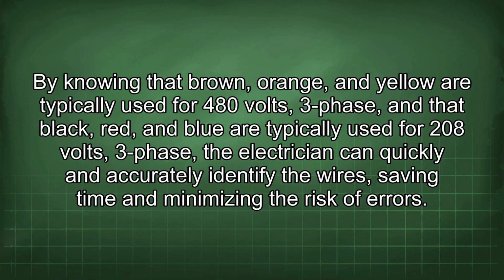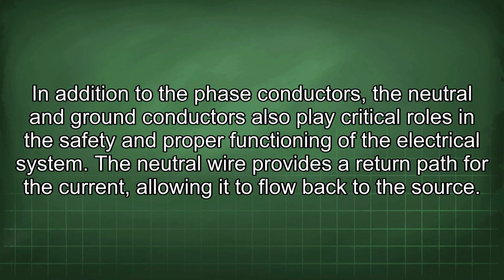By knowing that brown, orange, and yellow are typically used for 480 volts, 3-phase, and that black, red, and blue are typically used for 208 volts, 3-phase, the electrician can quickly and accurately identify the wires, saving time and minimizing the risk of errors. In addition to the phase conductors, the neutral and ground conductors also play critical roles in the safety and proper functioning of the electrical system.